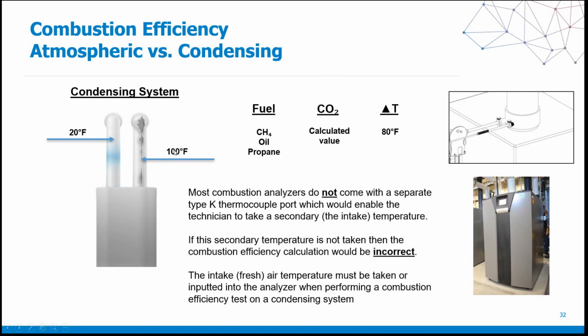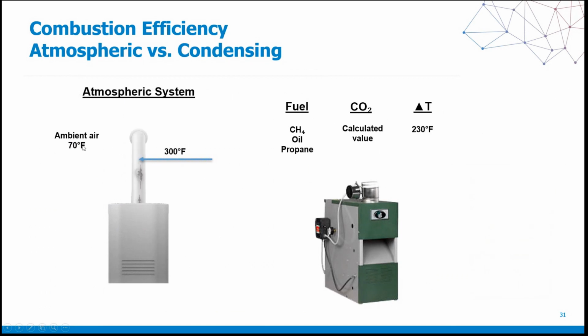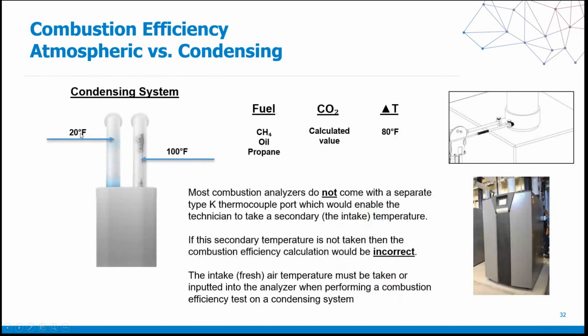If, for example, on the previous example here, we use the 70-degree ambient air instead of the 20-degree air that we see here, which is from our fresh air intake, our delta T would be wrong. For combustion efficiency, our delta T is 80. That is subtracting the 20 from the 100, which gives us a delta T of 80. If we took the 70-degree ambient air and subtracted it from the 100, that would have given us a delta T of 30, and that would be wrong. And thus, we would have the wrong combustion efficiency.